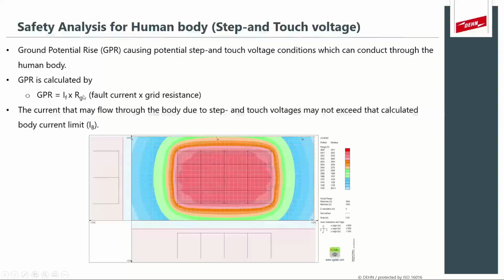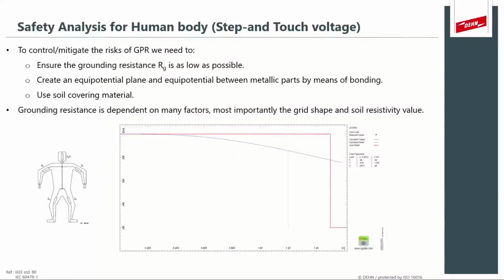Now, in this graph, we can actually see the ground potential rise on the top view, and the current that may flow through the body is dependent on these voltage differences. So this is the ground potential rise. It's not the actual step voltage. It's just the potential rise that you see at ground level. As I said, the whole danger and hazard is around the ground potential rise. To keep the ground potential rise, or the voltage that you would experience at ground level, as low as possible, we must ensure that the grounding resistance is as low as possible. Remember, the formula is Ohm's law.